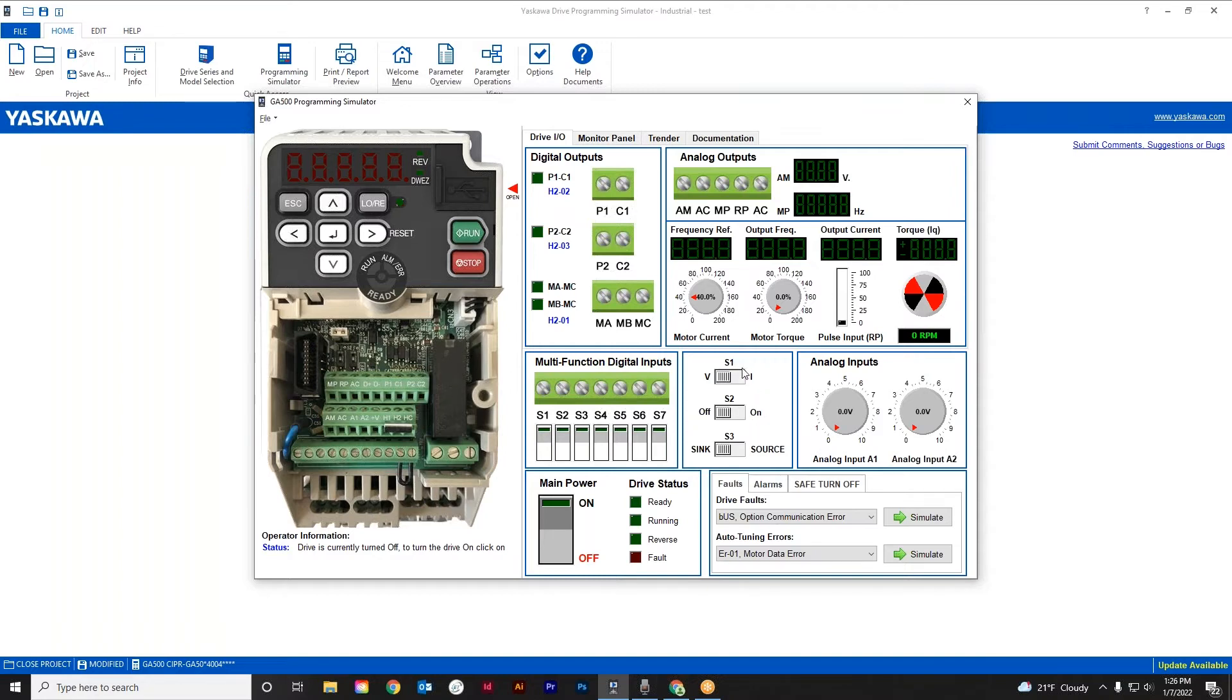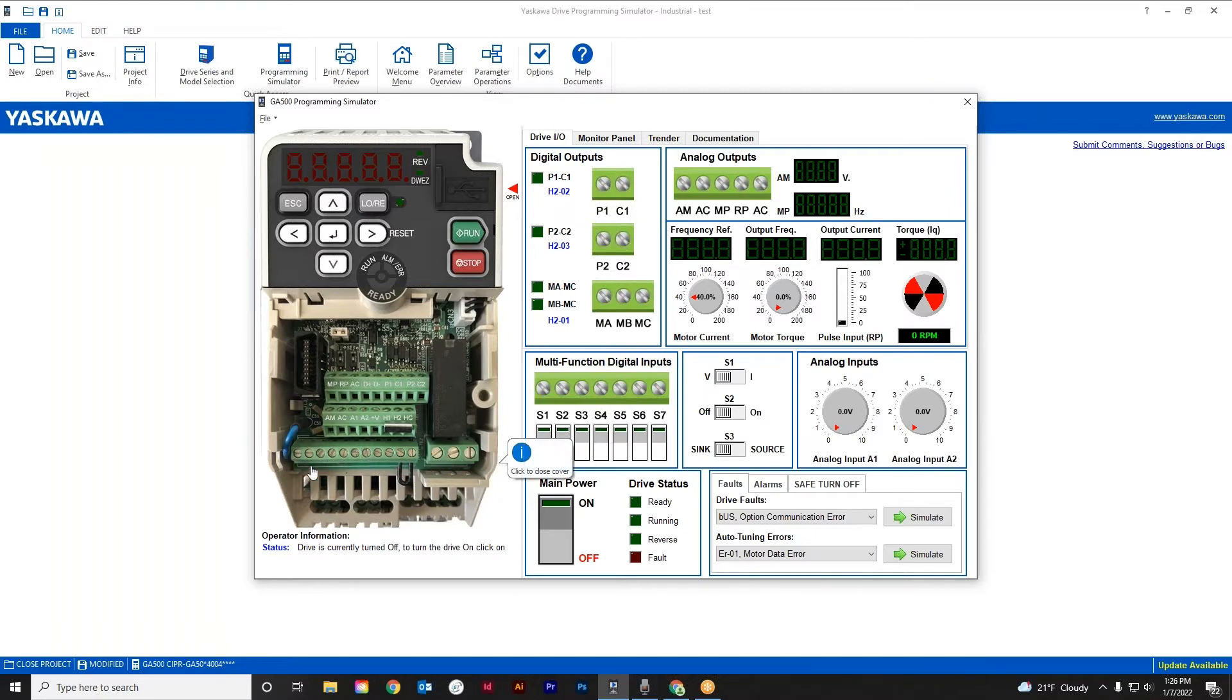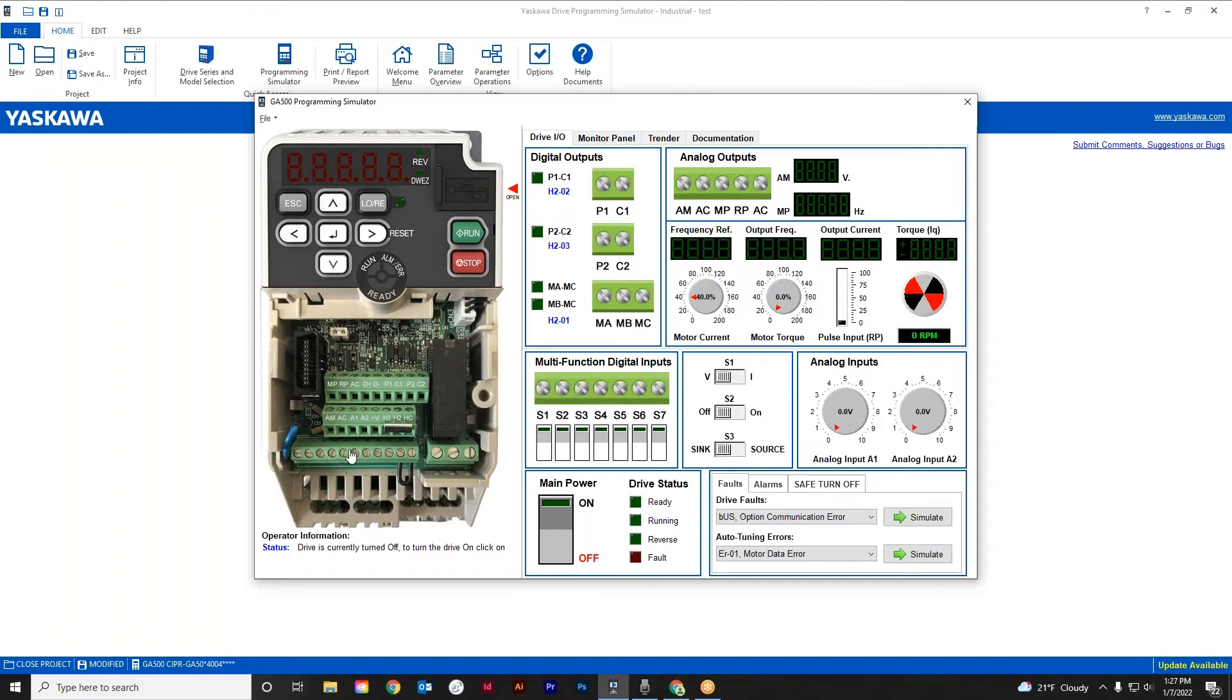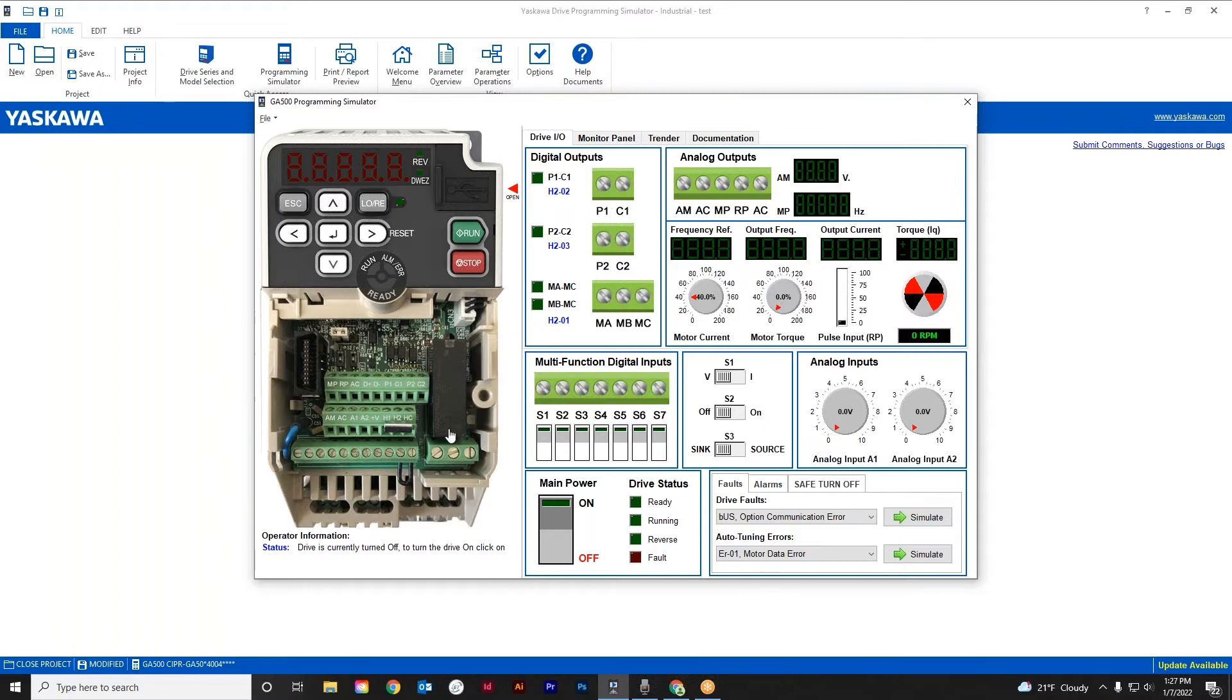Over here we're referencing some S switches. And those switches, actually in real world, are physically located right here. This is S1, that's S2, and this is the S3. So those three switches are actually represented over here. So it's kind of nice. So again, inside of here you've got these terminals, which obviously you can't see, but they're represented here through S1 through S7. These are the actual field connections, the actual where you bring your start-stop wires, your remote reset, that kind of stuff, into these S terminals. Those are the ones that are down here on the left, on the bottom. Also down here on the bottom are, again, you can't see these numbers, but they're the MA, MB, and MC. That's these right here. That's your relay output. This is a Form C, 1 amp, 250 volt rated relay that's sitting there ready to be used. And that's what this is representing. And of course there's a few other things in here we'll talk about as we progress.